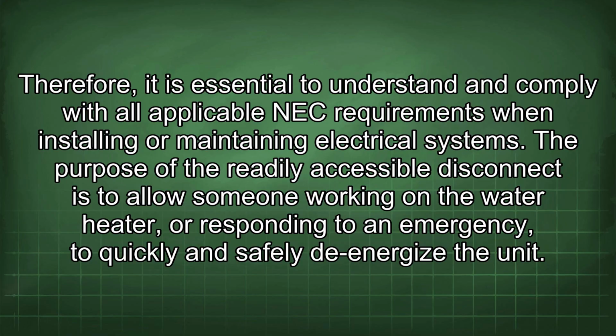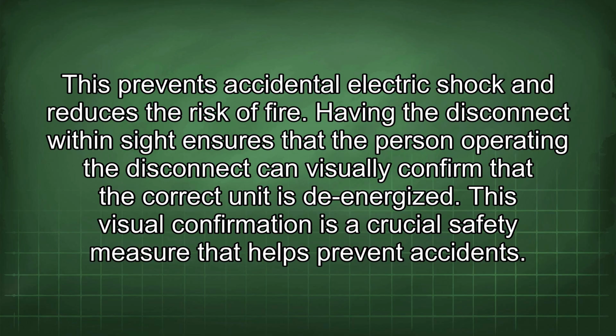The purpose of the readily accessible disconnect is to allow someone working on the water heater or responding to an emergency to quickly and safely de-energize the unit. This prevents accidental electric shock and reduces the risk of fire. Having the disconnect within sight ensures that the person operating the disconnect can visually confirm that the correct unit is de-energized. This visual confirmation is a crucial safety measure that helps prevent accidents.